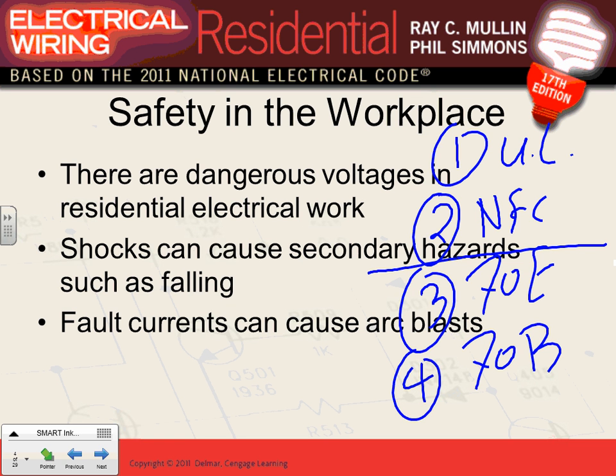As a matter of fact, yesterday I stopped by an electrical contractor working on a project. They wanted to modify it, and the electrician opened a 400 amp, 240/120, 3-phase center tap delta disconnect, and you're staring right at the big cover and fuses. I wasn't carrying tools - I was there because we wanted to add a generator to the plant, and I was thinking, wow. So even when you're not carrying tools, just there to modify the system, if somebody drops a wrench, you're exposed to arc flash.